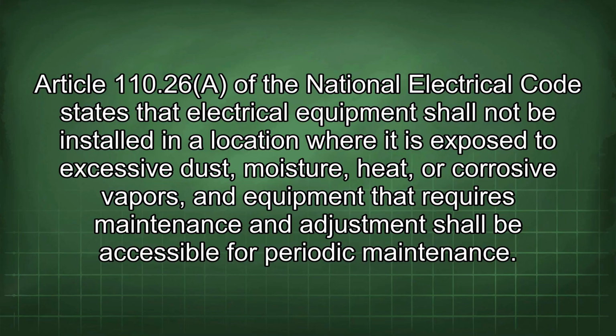Article 110.26 of the National Electrical Code states that electrical equipment shall not be installed in a location where it is exposed to excessive dust, moisture, heat, or corrosive vapors, and equipment that requires maintenance and adjustment shall be accessible for periodic maintenance.